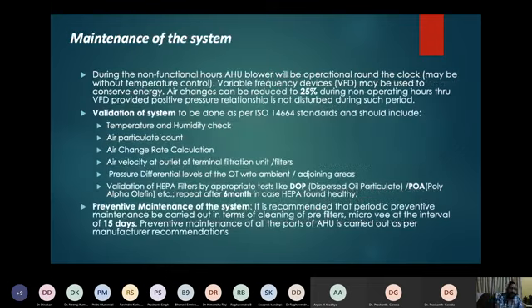Coming to maintenance, there is another circular stating that periodic preventive maintenance of the system should be done, like temperature and humidity check, air particulate count, air change rate calculation, air velocity, pressure differential, and validation of the HEPA filter fixed to the laminar flow. All this preventive maintenance should be part of the maintenance system.